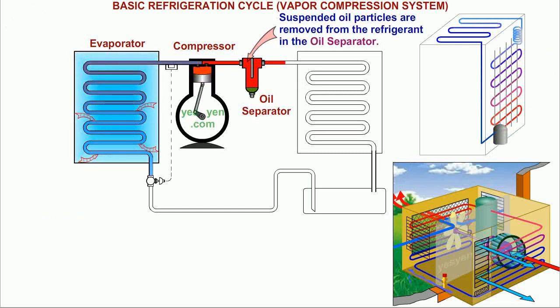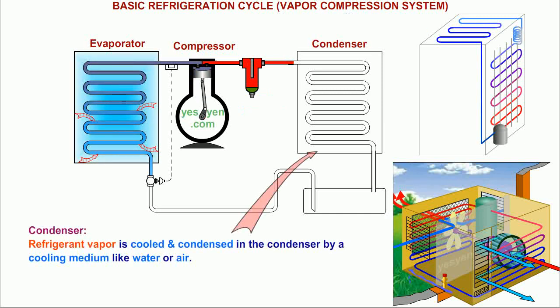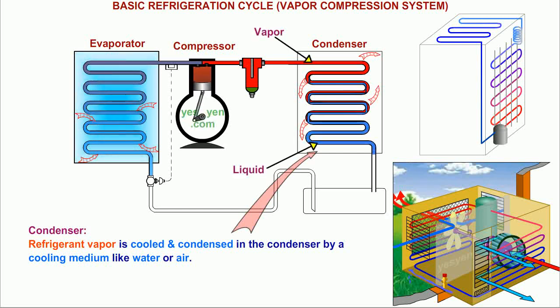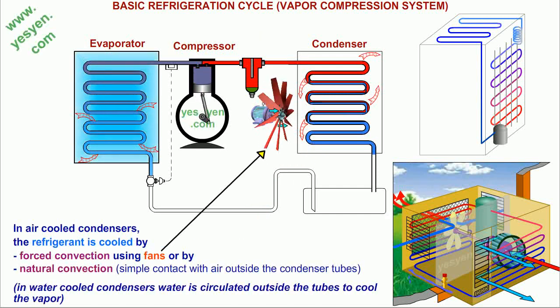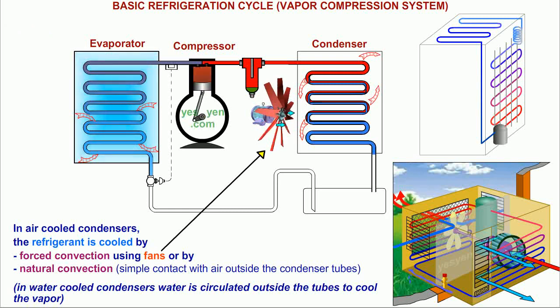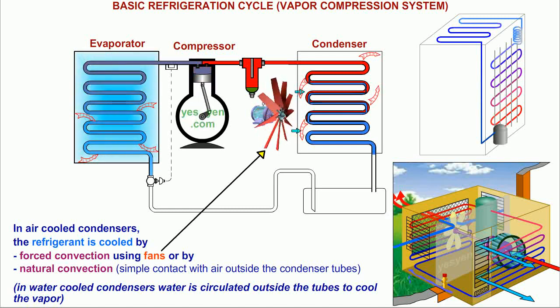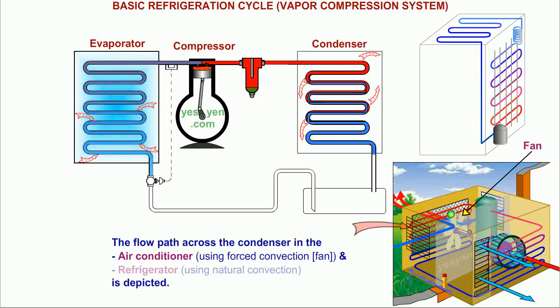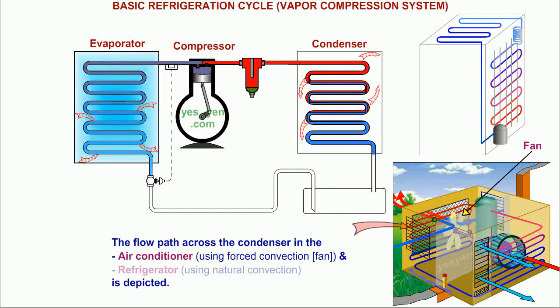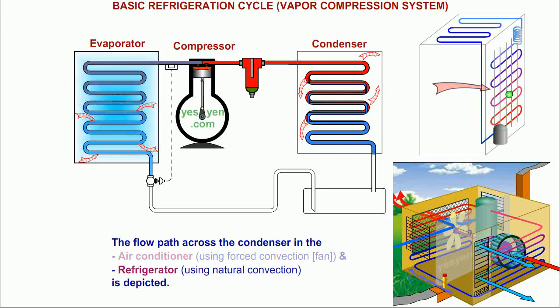Suspended oil particles are removed from the refrigerant in the oil separator. Condenser: Refrigerant vapor is cooled and condensed in the condenser by a cooling medium like water or air. In air-cooled condensers, the refrigerant is cooled by forced convection using fans, or by natural convection. In water-cooled condensers, water is circulated outside the tubes to cool the vapor. The flow path across the condenser in the air conditioner using forced convection and refrigerator using natural convection is depicted.